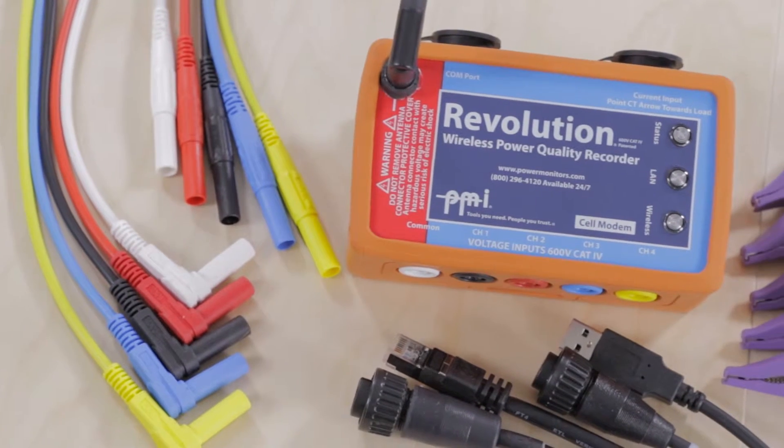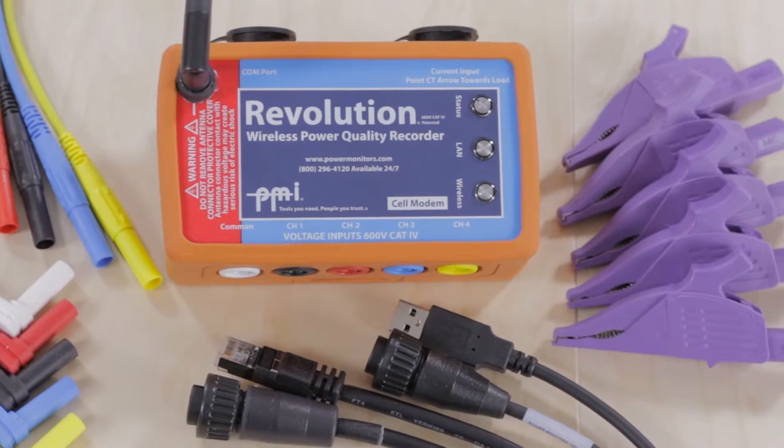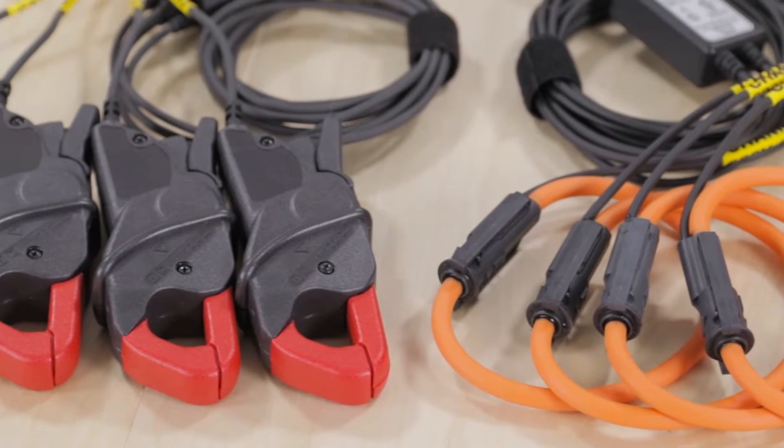The Revolution is PMI's high-speed transient capture power quality monitor with industry-leading communications capabilities, including USB, Ethernet, Bluetooth, and cellular connection. It has up to one gigabyte of memory, a one megahertz sampling rate for voltage, and 250 kilohertz for current. The Revolution comes with everything you need to get up and running; however, there is additional equipment that can extend its usability, such as PMI's Flex CTs and TLR current clamps.